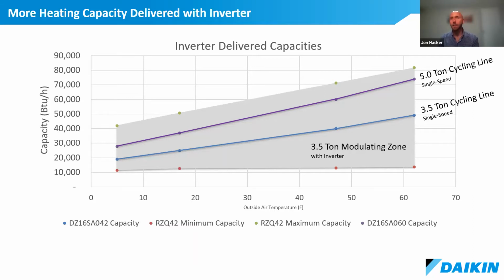But by adding an inverter to our system, we can significantly increase the amount of heat that can be delivered when it's cold out. So if you look at that 5-degree condition for the inverter product, it can deliver in excess of 40,000 BTUs, so more than twice the heat when it's cold out. And that's really important, and that's what's allowed us to use combined inverters with heat pumps and using them in the Northeast for when it's cold out.